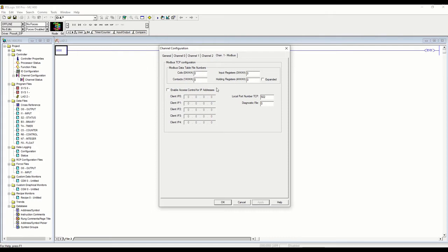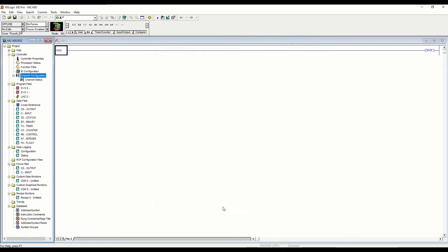For example, if we wanted N7 to be mapped to holding register 40007, we could put that in here — just put data file 7. But we're not going to do that since this is going to be our master doing the polling. Just so you know, the MicroLogix 1400 can act as a Modbus slave and you can map data files to the registers. So we'll hit apply and hit okay.